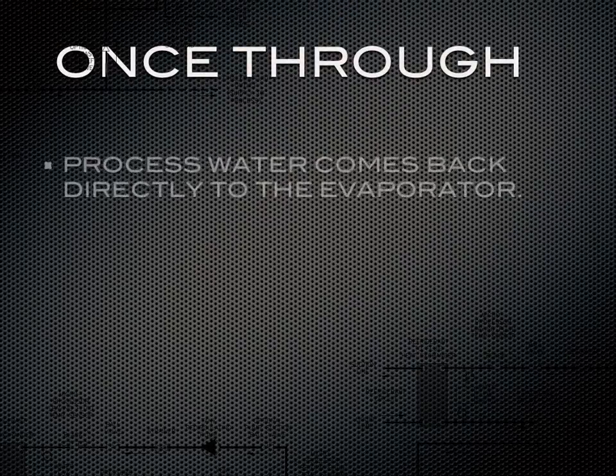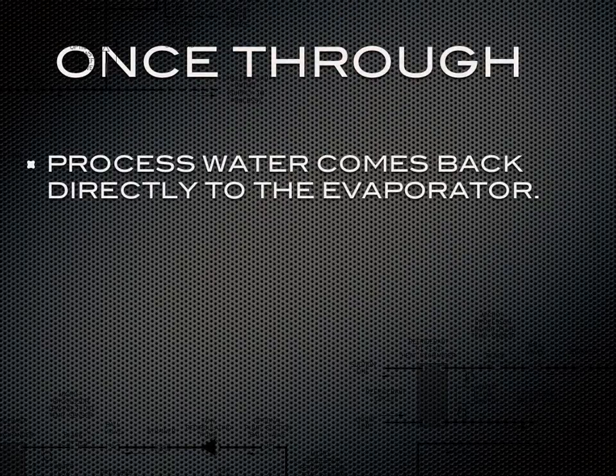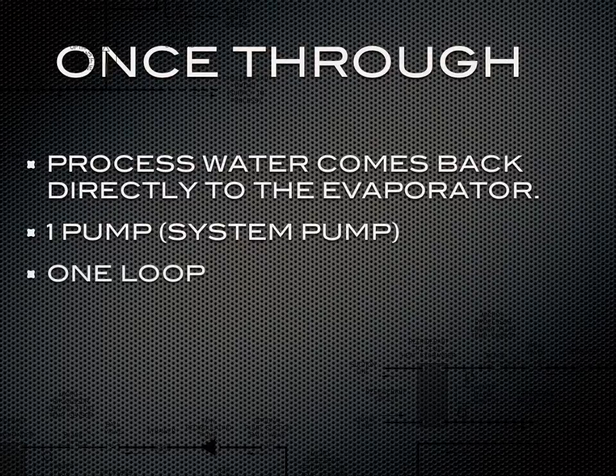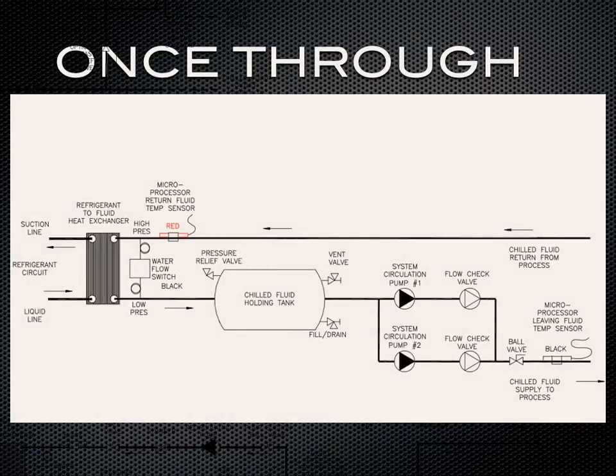Let's go over what a once-through chiller is. A once-through chiller is where the process water comes back directly to the chiller evaporator. These systems typically have one pump, and that one pump will create one loop. Let's go over a drawing of a PACT package chiller set up as a once-through. You're going to notice that the tank is on the supply side of the process, and there's one in and one out. One thing to keep in mind is that you always want to store cold fluid to your process. You don't want to put your tank on the return side and store warm fluid.